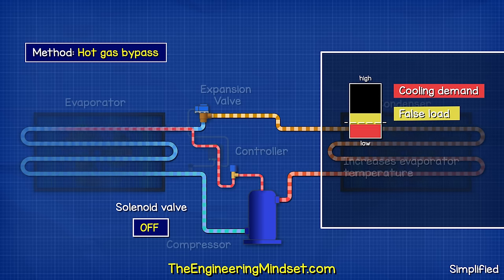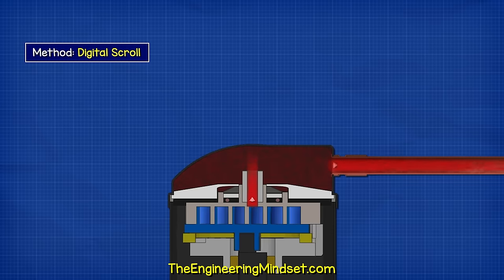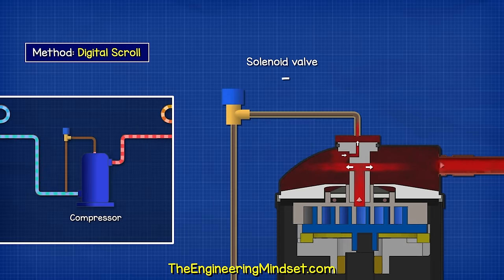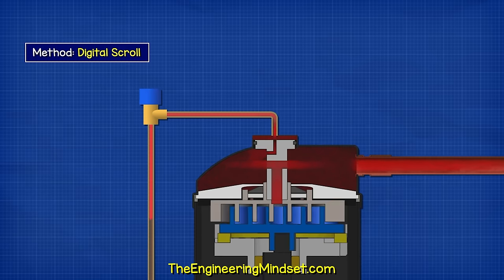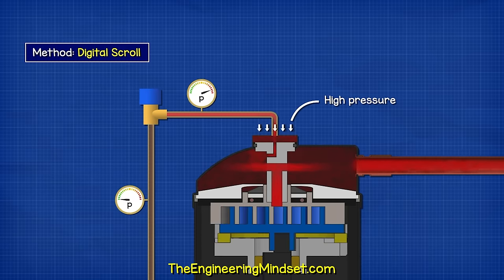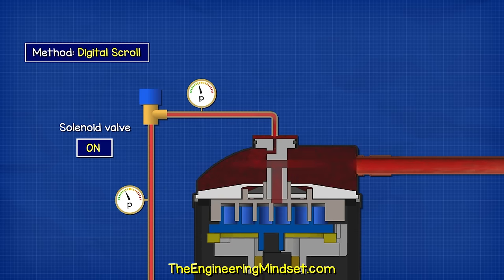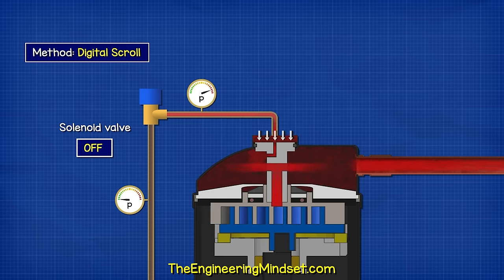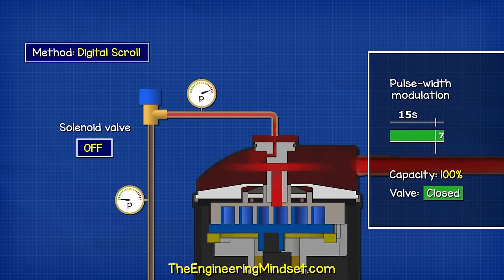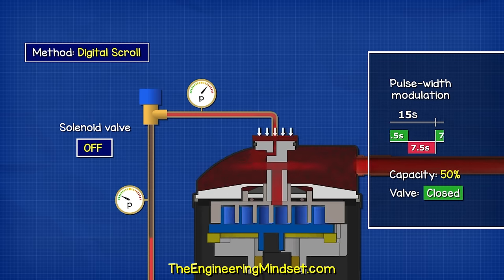Another common design is the digital compressor. A solenoid valve recirculates refrigerant back into the suction line. The fixed scroll can move up and down. The pressure within the dome holds the fixed scroll down but a solenoid valve can open to release this pressure back into the suction line. During this moment, the scrolls will disengage a tiny amount and so no refrigerant will be compressed in this time but the motor keeps running. After a short duration, the valve then closes, the pressure builds up again, and this pressure will force the scroll down and so the compression continues. We control this in 15 second intervals. So, if you need 50% capacity, then the scroll will engage for 7.5 seconds and then disengage for 7.5 seconds.